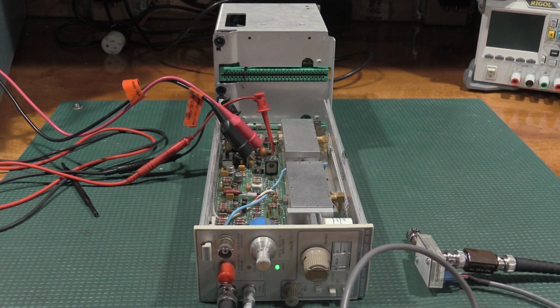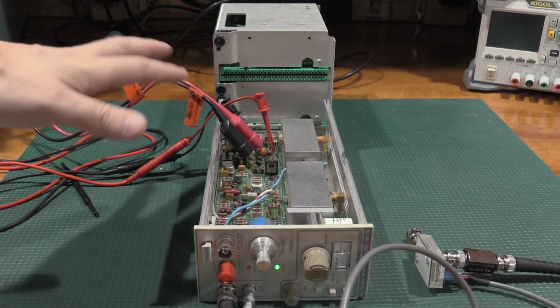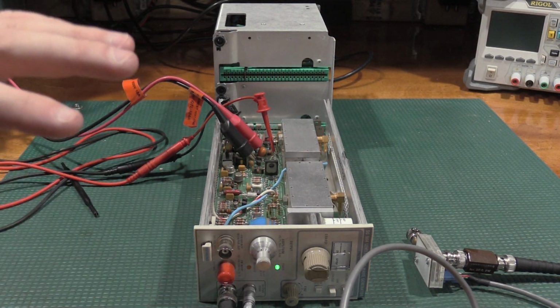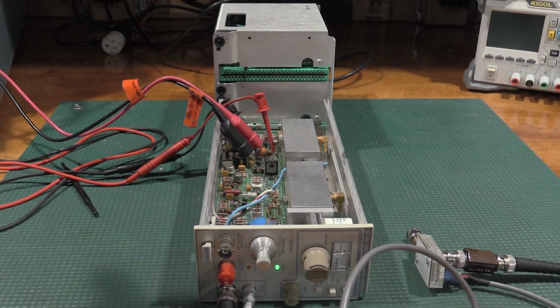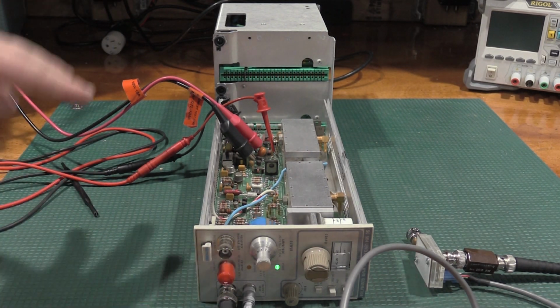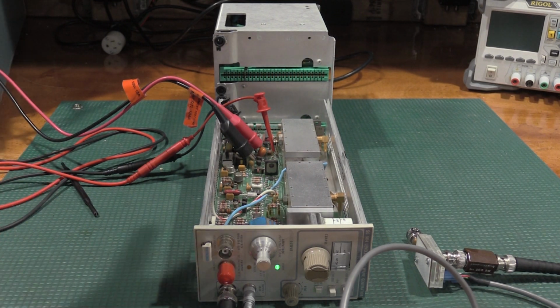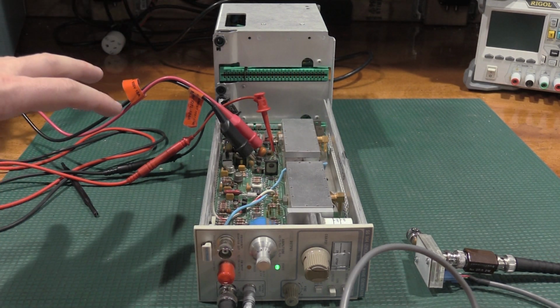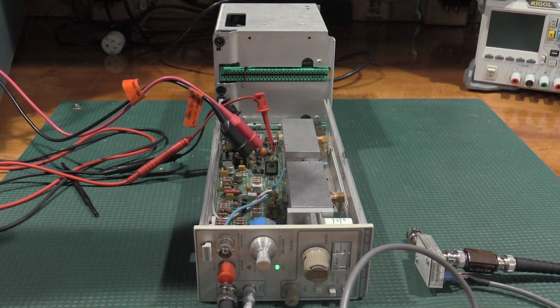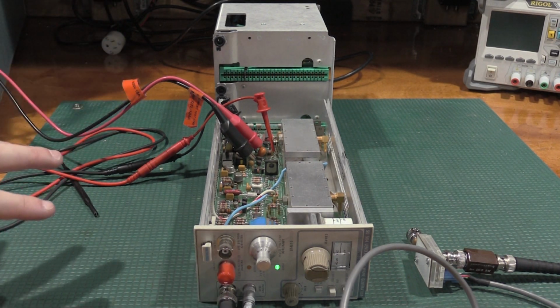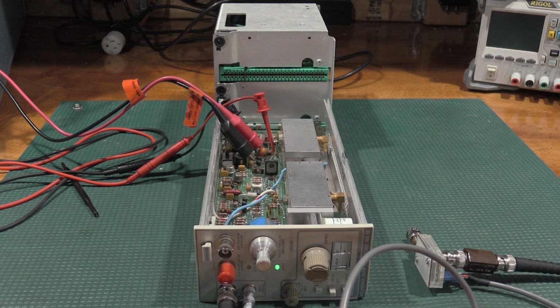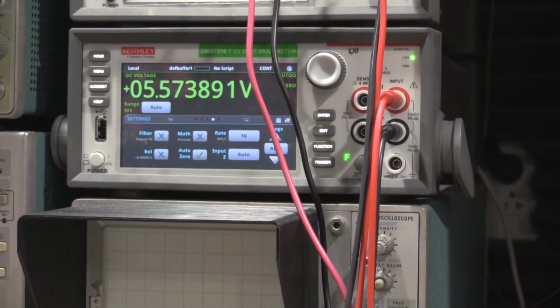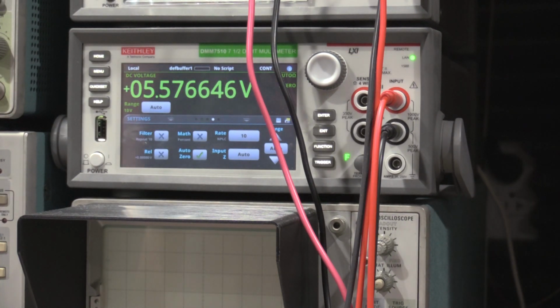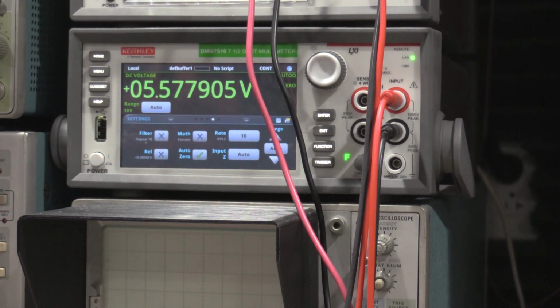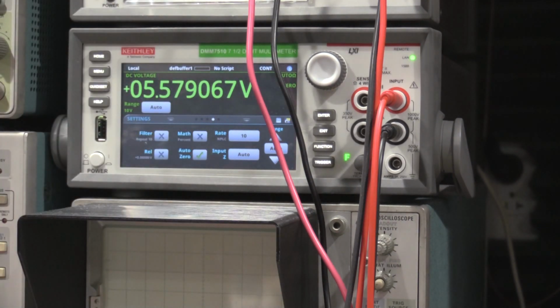So if there's any questions on how to hook this up, don't do it. This could potentially damage things, especially if you feed a negative voltage into the DC load. The pass elements in the DC load are not going to like that. So this has to be hooked up in the correct polarity, which is not intuitive for what needs to happen, but it's letting me proceed with the calibration. That's why it looks kind of funny. 5.5, that's exactly what we're expecting. So that is working as normal, and I'm unleveled, which is correct.